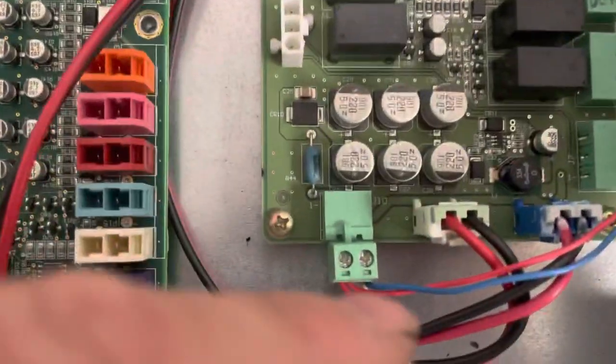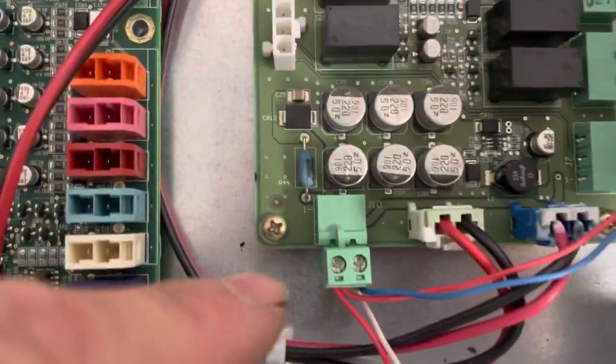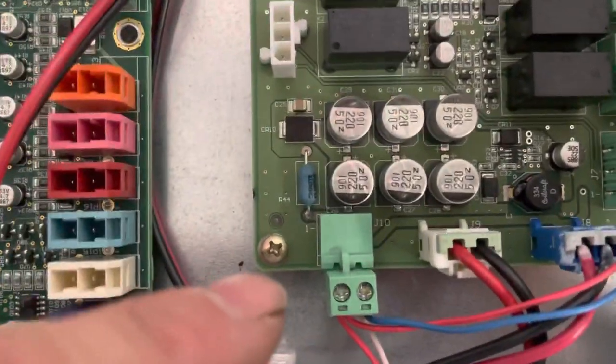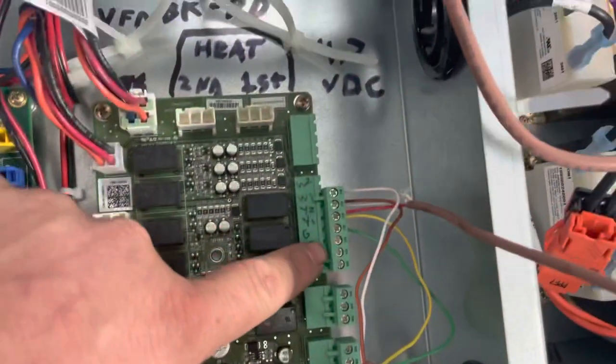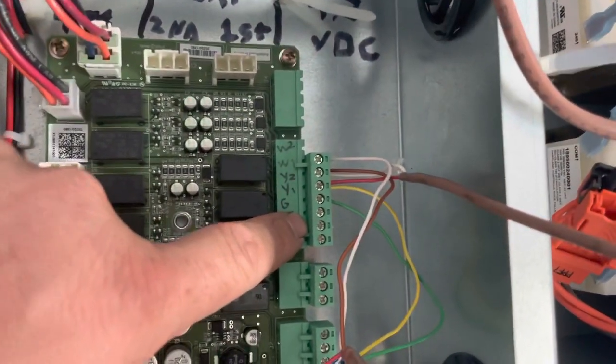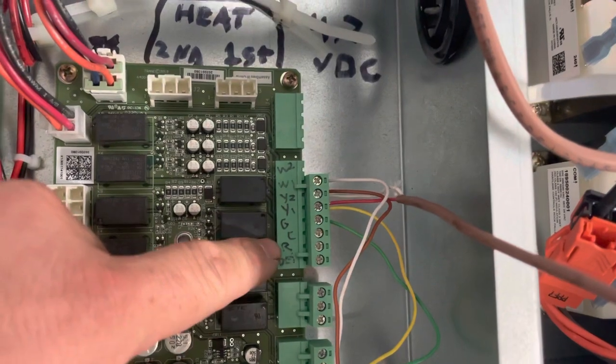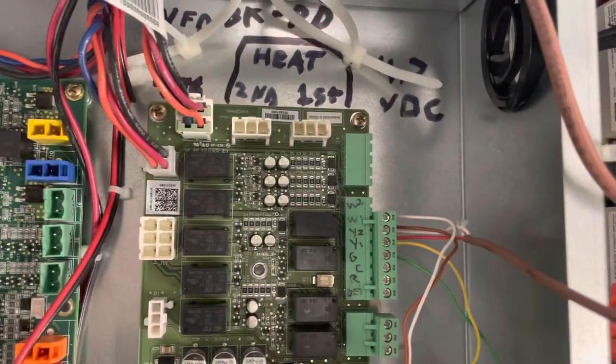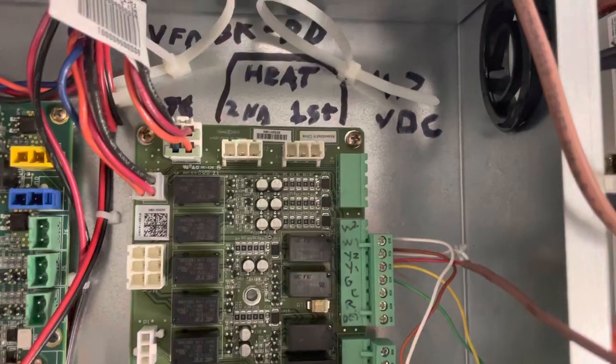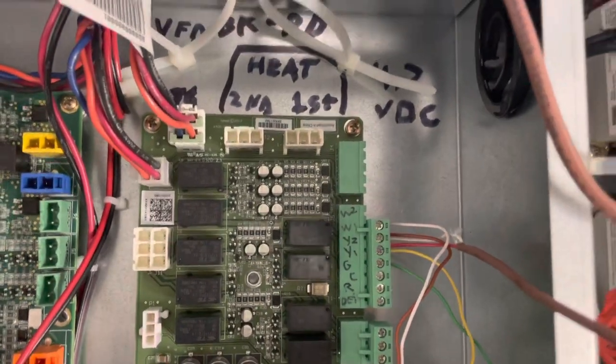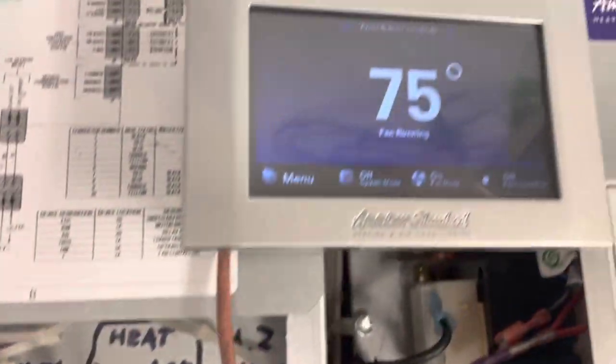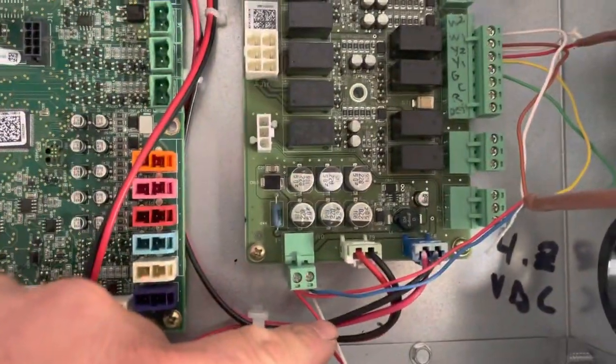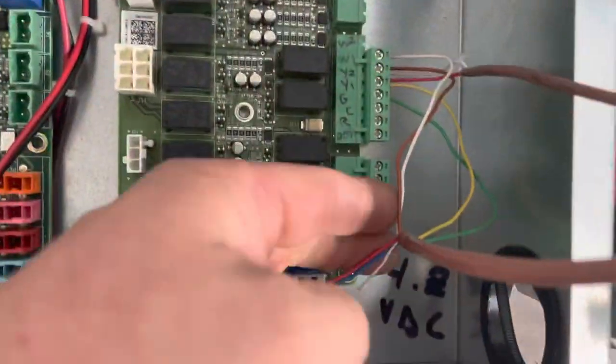Important note: don't take your thermostat power off of here, the R and the C. Those points on there are only rated for I think it's 300 milliamps, very small amount, so it's not enough to run the thermostat. Don't hook it up to there. Grab your power off the J10 plug and hook everything else up here.